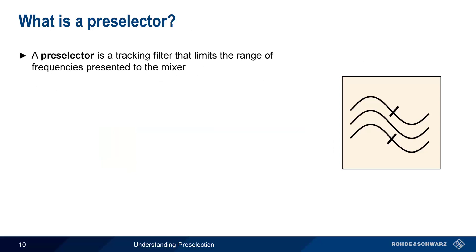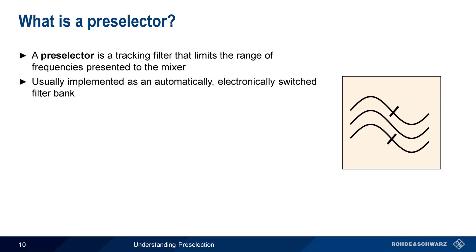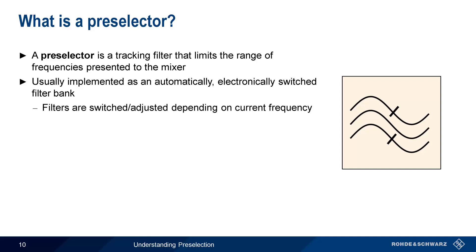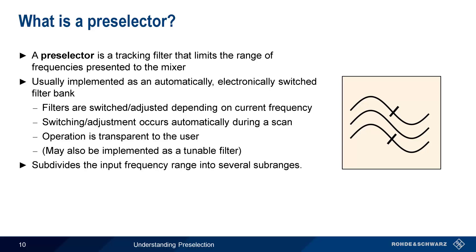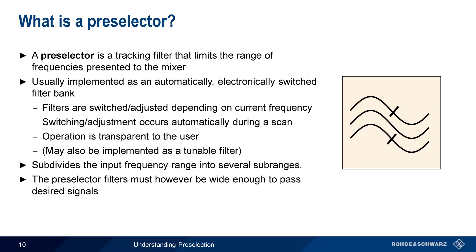A preselector is a type of tracking filter that can be used to limit the range of input frequencies presented to the mixer. Preselectors are usually implemented as an automatic, electronically switched bank of filters. The preselector selects or adjusts which filter to use based on the current frequency of the instrument, and automatically switches from one filter to another when the operating frequency changes — transparently, without any user intervention. Note that even though most preselectors are implemented as a bank of filters, a preselector could also be implemented using a single, tunable filter. Due to the way a preselector operates, the input frequency range is essentially subdivided into several sub-ranges, one per filter. There is however a practical limit on the number and minimum width of these filters, since the preselector filters must still be wide enough to pass any desired signals without distortion.